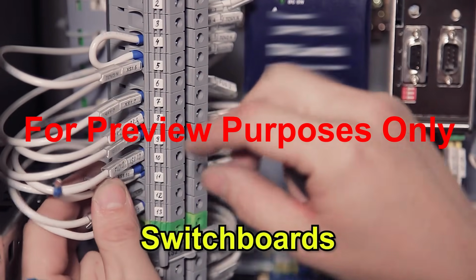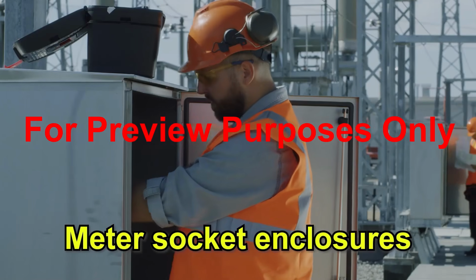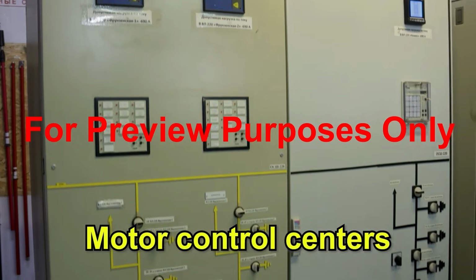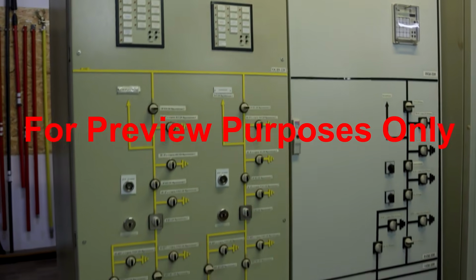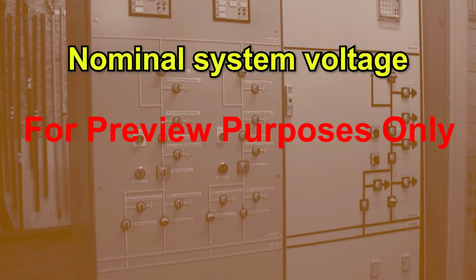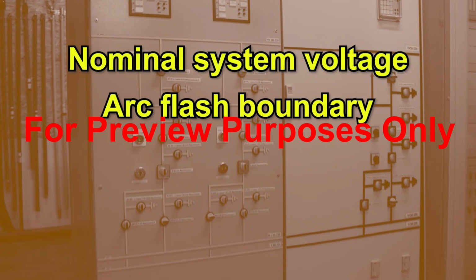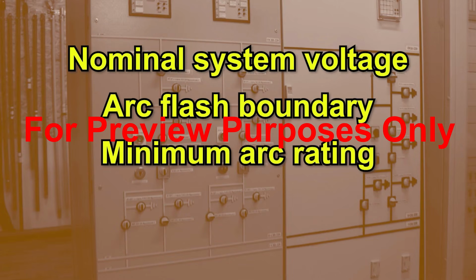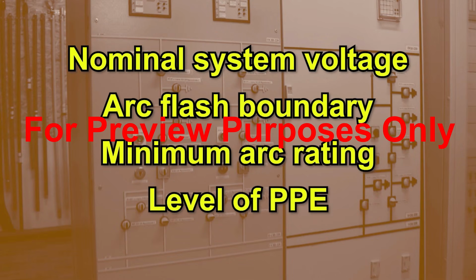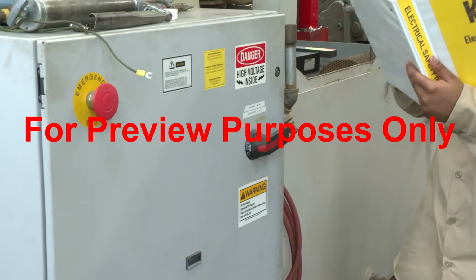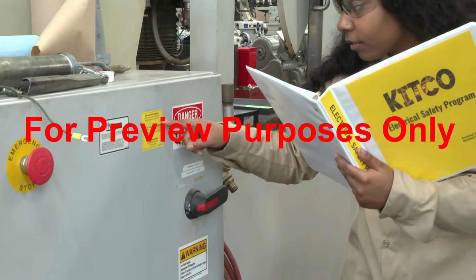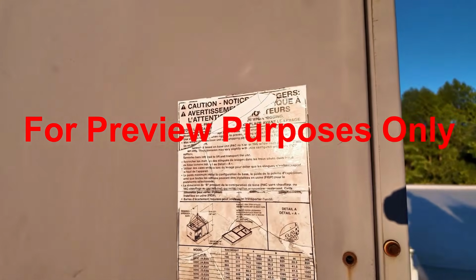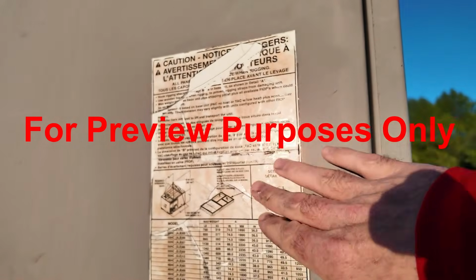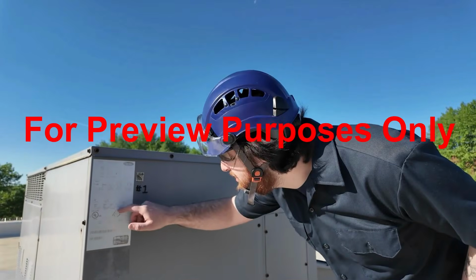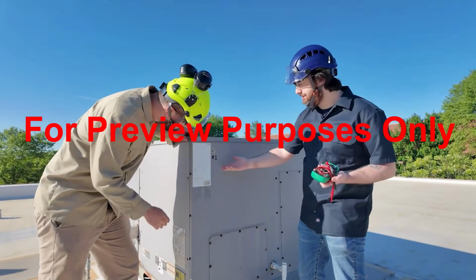All switchboards, panels, meter socket enclosures, and motor control centers should be labeled with their nominal system voltage, arc flash boundary, minimum arc rating for clothing, and the level of PPE that should be worn when working on the equipment. So it's important that the labels are legible. If a label isn't durable enough to withstand the environment it's in, or you have trouble reading it, notify your supervisor.